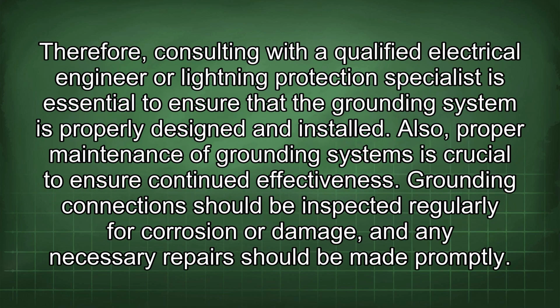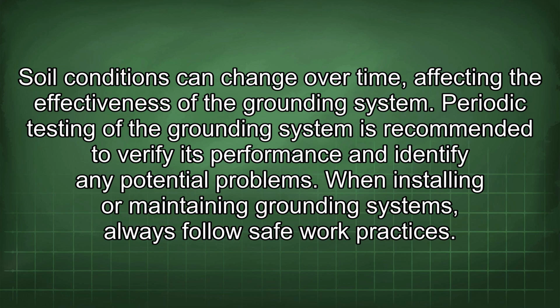Therefore, consulting with a qualified electrical engineer or a lightning protection specialist is essential to ensure that the grounding system is properly designed and installed. Also, proper maintenance of grounding systems is crucial to ensure continued effectiveness. Grounding connections should be inspected regularly for corrosion or damage, and any necessary repairs should be made promptly. Soil conditions can change over time, affecting the effectiveness of the grounding system. Periodic testing of the grounding system is recommended to verify its performance and identify any potential problems.